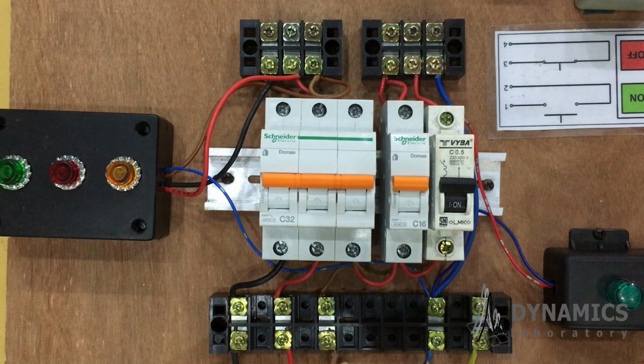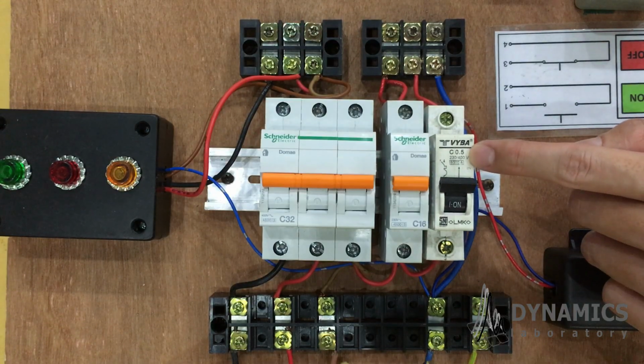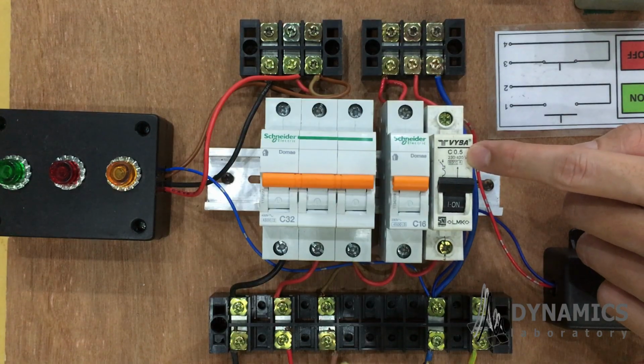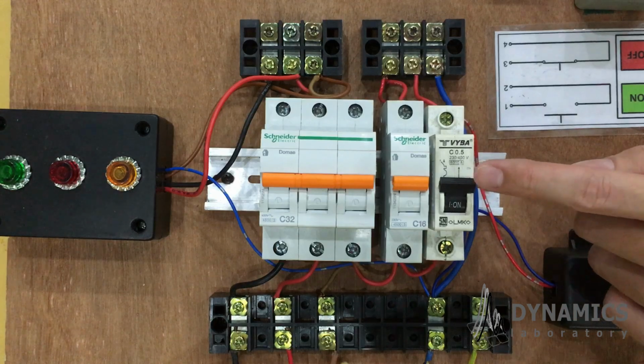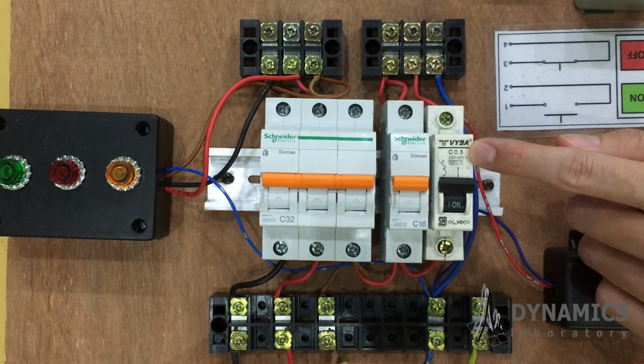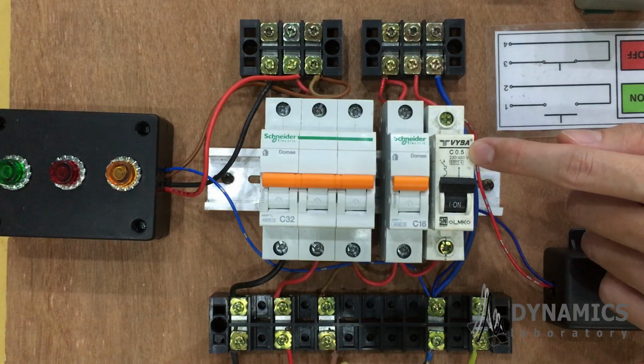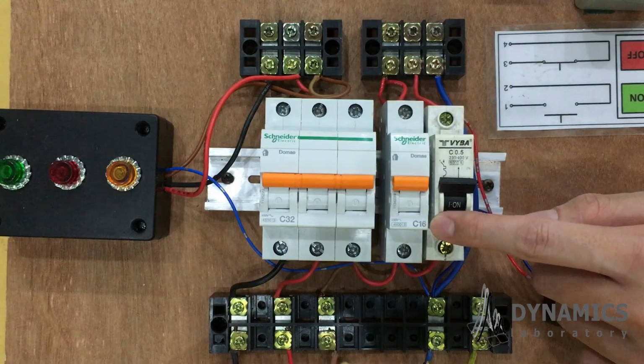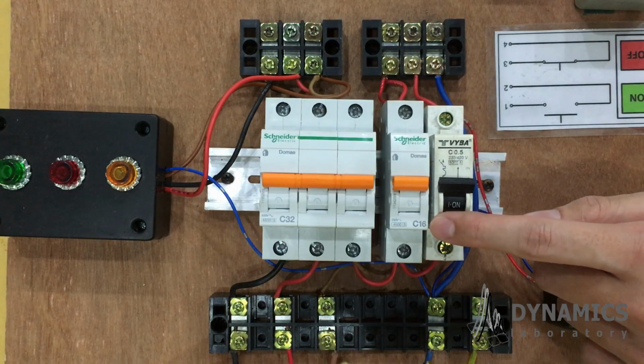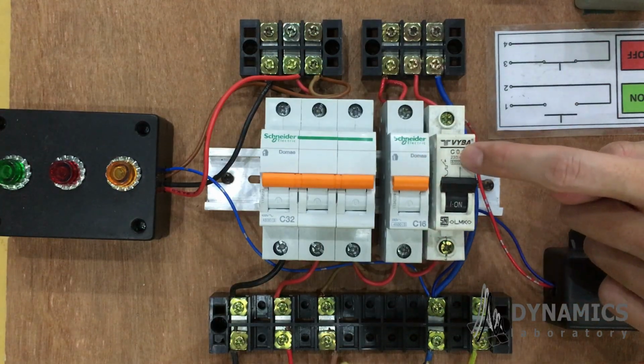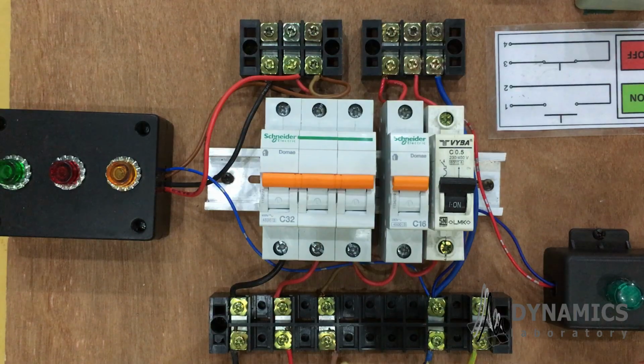Circuit breaker. We have 3 circuit breakers with different capacity. Do you still remember how to determine the maximum current capacity of a circuit breaker? Yes, we can see from the number after the C alphabet. The first one, the circuit breaker with black lever, shows C0.5, which means the maximum current flow is only 0.5 ampere. The second one, C16, which means maximum 16 ampere. Both of these circuit breakers are called one-phase circuit breakers, because they only control one live terminal or one line.